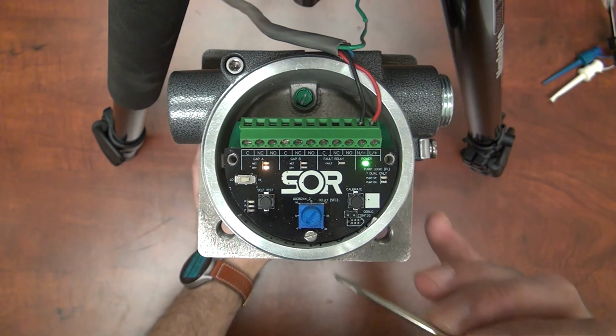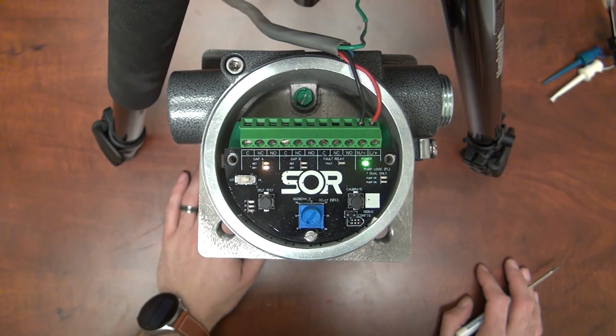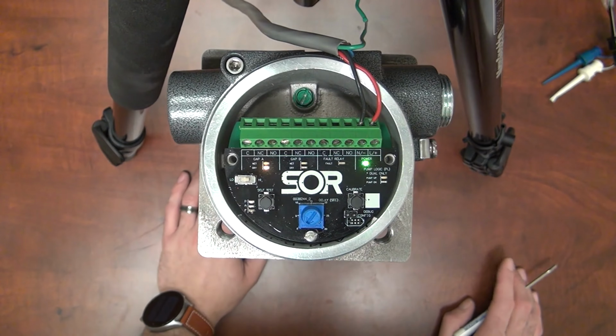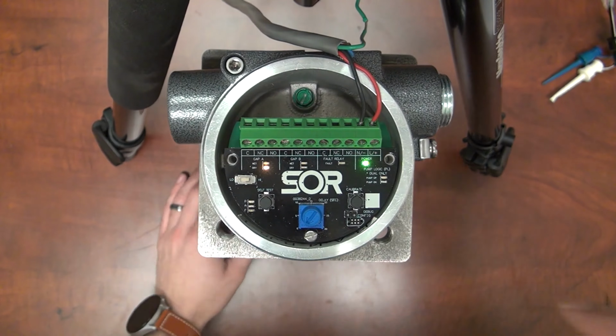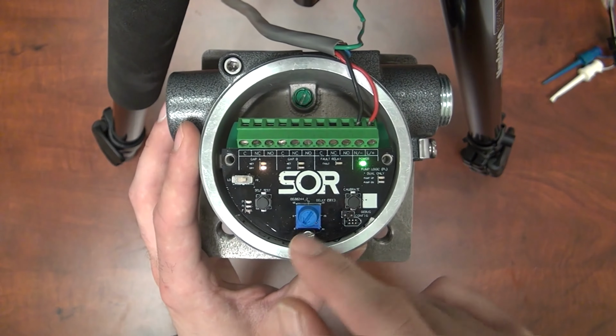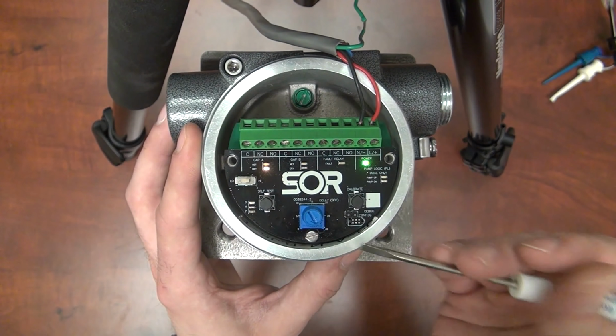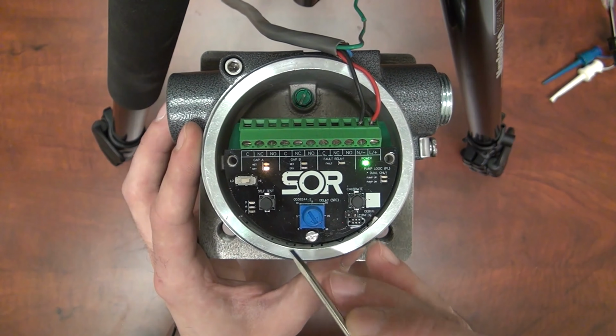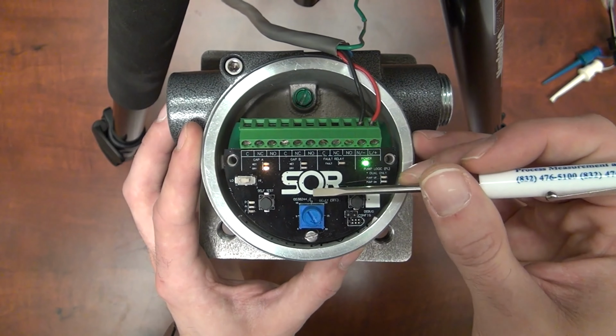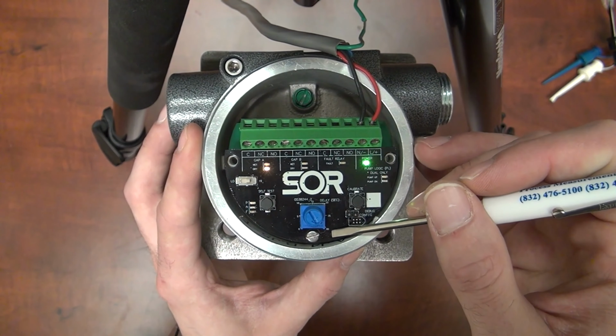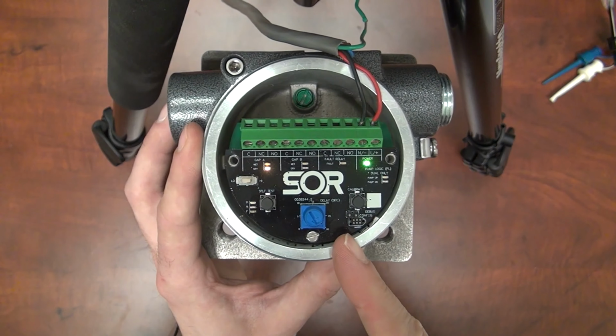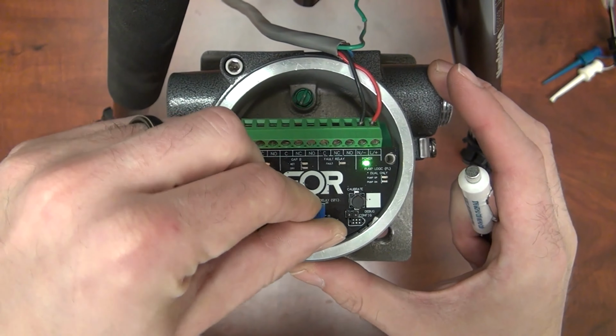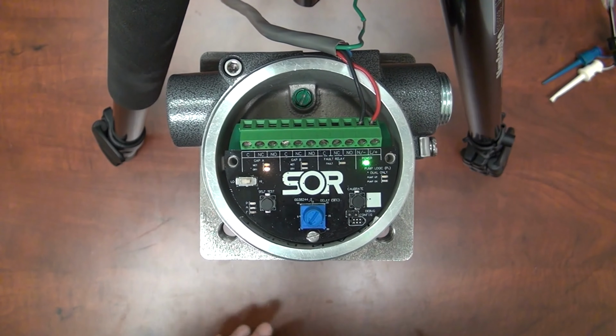For the next feature, we have the time delay dial, seen here. Each 2700 series comes with an adjustable time delay. It's an integral timer that starts when liquid level is either detected in or removed from the sensor cavity. The dial can be turned from here, pointing in the lower left corner, clockwise down to the lower right corner. There are labels around the outside of the interface labeled 0, 5, 10, 15, 20, 25, and 30 seconds. With the dial turned all the way clockwise, it will be at 30 seconds. Turning it counterclockwise to 0 turns the time delay off.